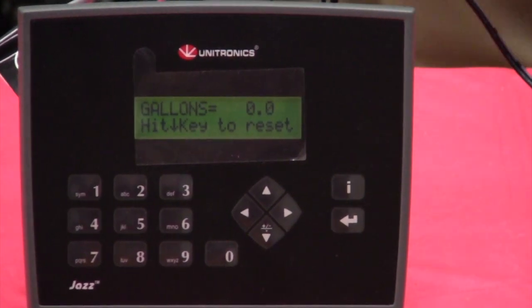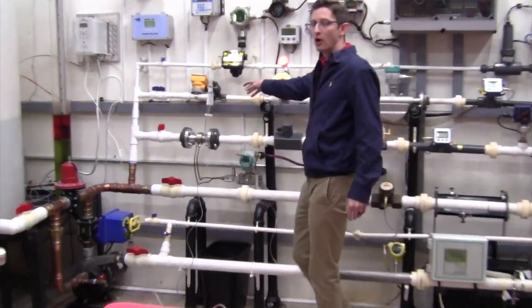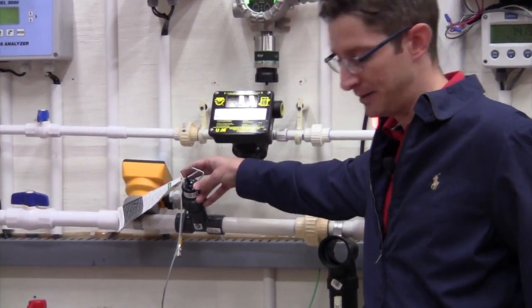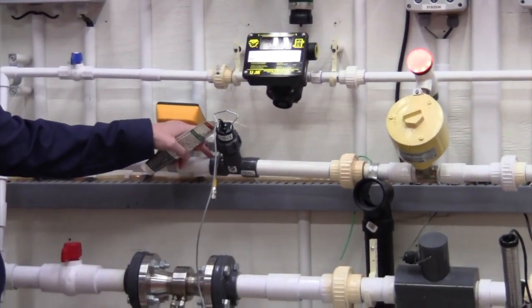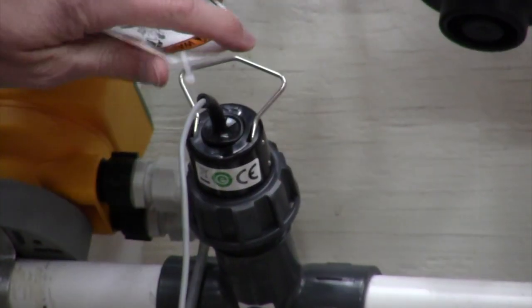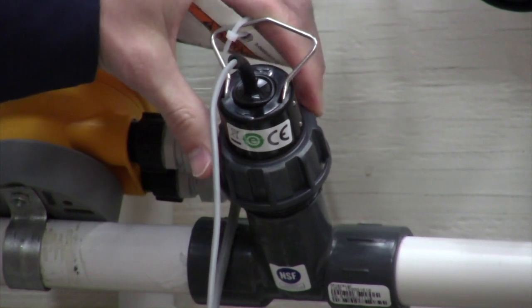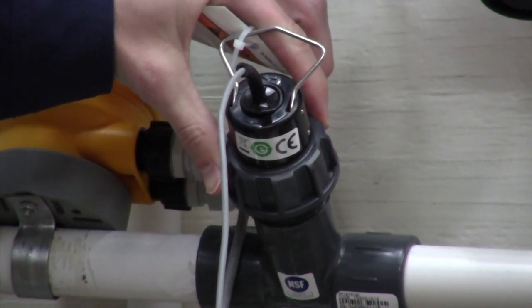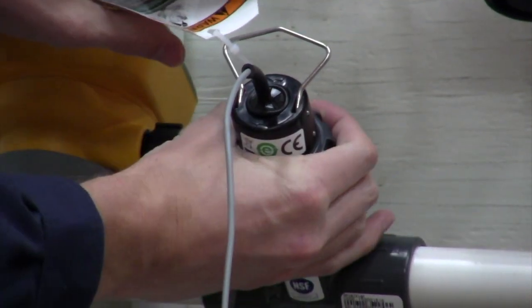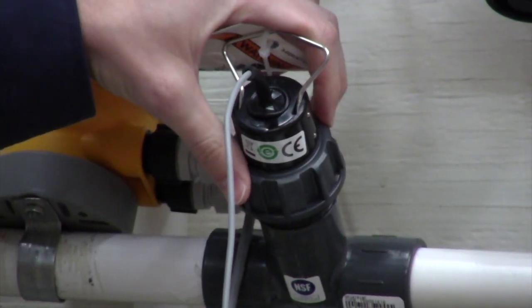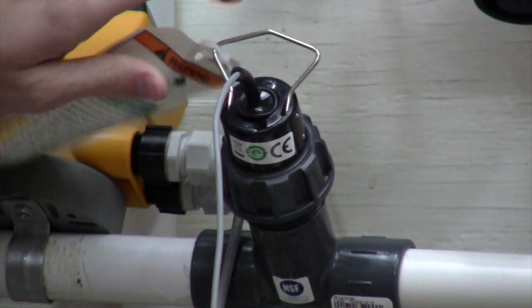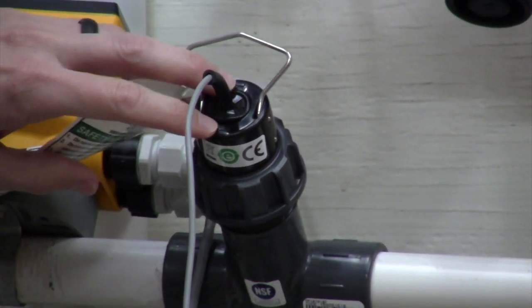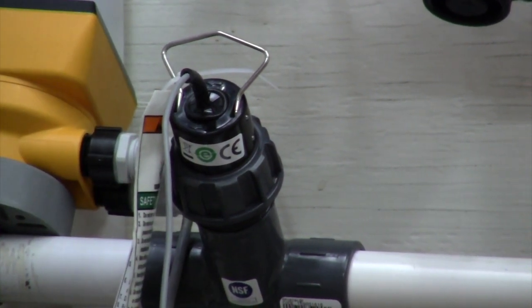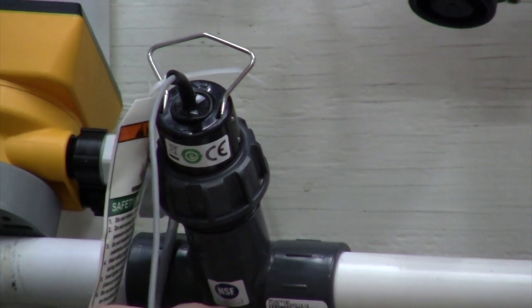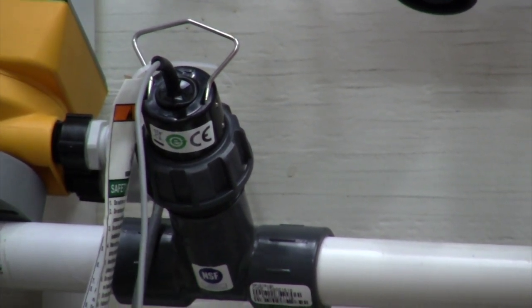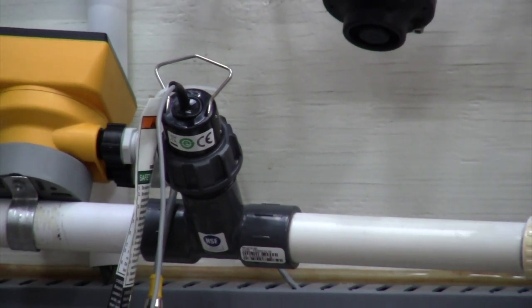From here, we've installed our paddle wheel flow meter into the 1-inch line, and that's installed in a 1-inch T, just like I showed you earlier. Two things to note. Whenever you install this meter, you line the grooves up on the inside of the flow meter and on the T, and then you crank down the fitting on top to hand tight, and then go an additional 1/4 turn. You will also notice flow arrows on top of this flow meter. The flow arrows are completely unimportant. We just need to make sure that the paddle wheel inside the T is perpendicular to flow, so that when flow passes by, it will cause that paddle to spin.